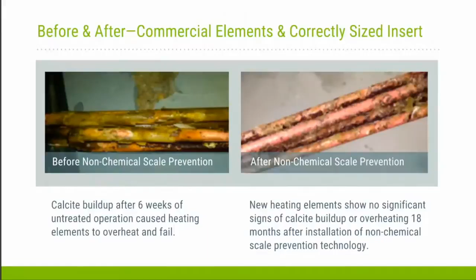We let it run. And it ran. And it ran. After 3 months, we went in and pulled out the heating elements. Again, this is the first time this water heater has run this long without a failure. The picture on the right shows one of the heating elements that we pulled out after 3 months. There were some tiny bits of scale on it, but absolutely nothing compared to what we had seen. Again, you can compare the left photo to the right photo.